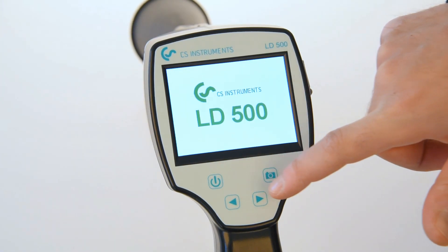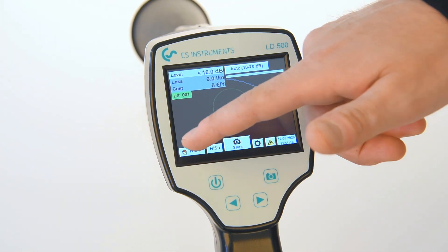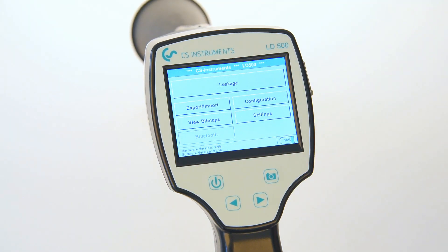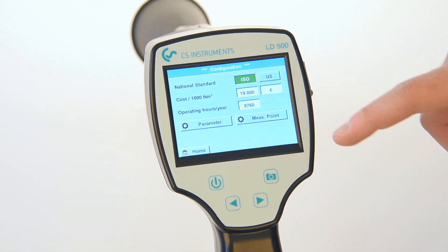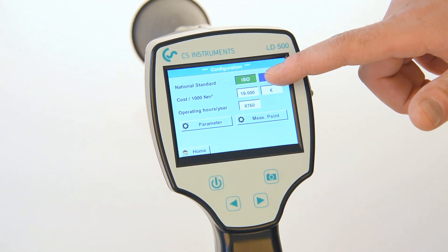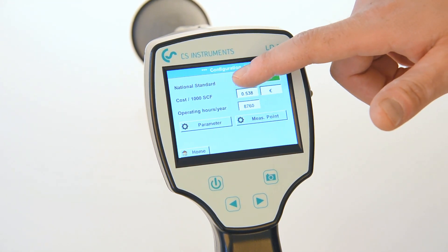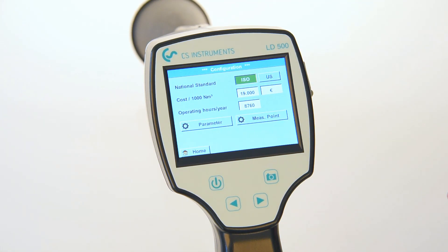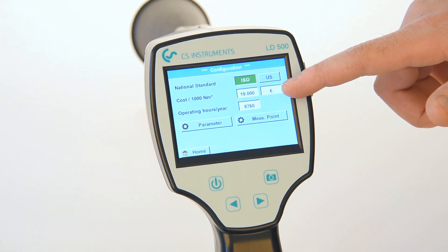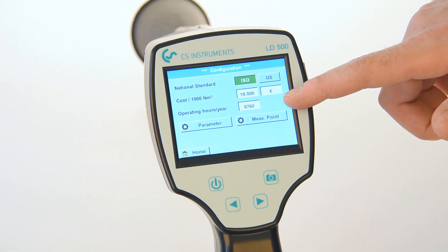To start off, we would like to show you how the configuration of the instrument works. In order to get to the configuration menu, you need to press the home button tab on the main screen. Once inside the configuration menu, the instrument can be set up individually for each site. The national standard can be selected as well as the cost per volume, the local currency, and the annual running hours of the compressed air system.